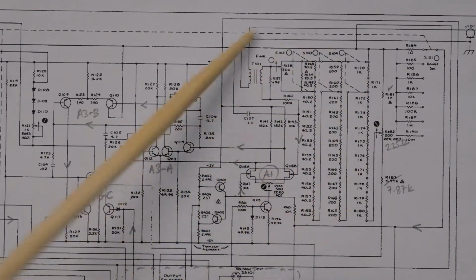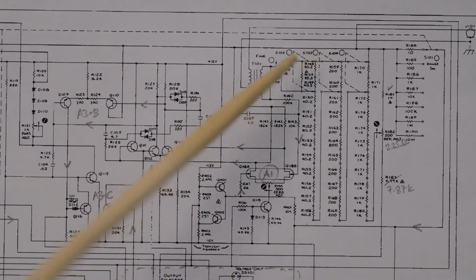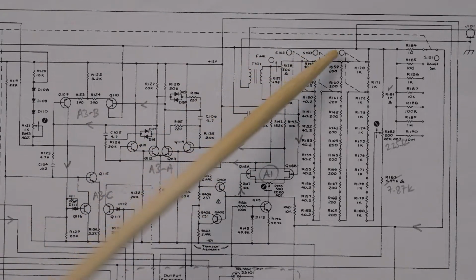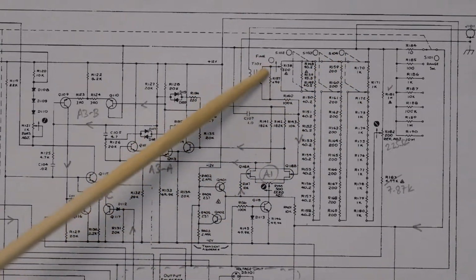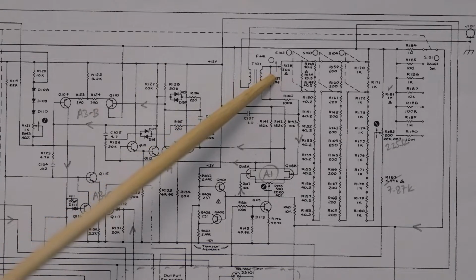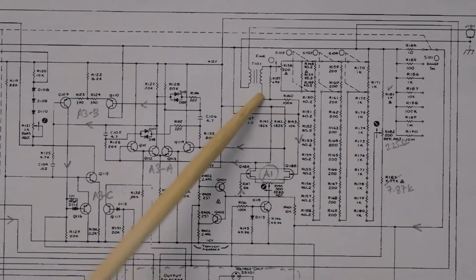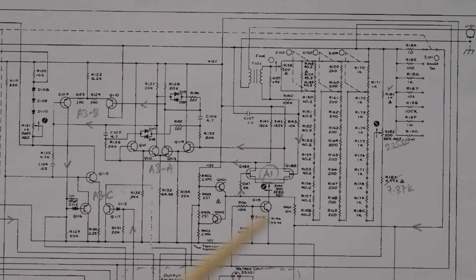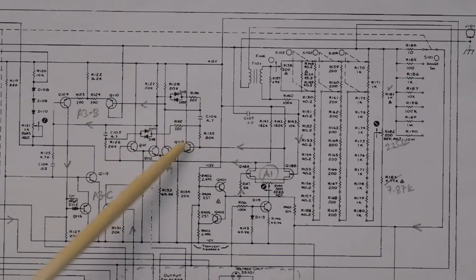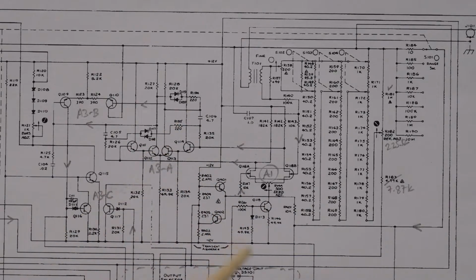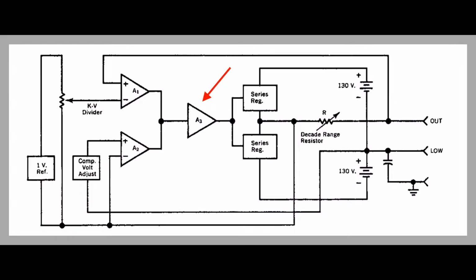So the Kelvin Varley divider is this big resistor network. It's controlled by the 3 switches, which can select different digits from the MSB down to the LSB, plus a fine tune, which is the final potentiometer, which is a variable one, which gives you the 0.02% full scale adjustment. So the output of this Kelvin Varley divider goes into this A1 amplifier, which is really this main amplifier here, whose second input is basically the feedback of the output that is coming from the current source load. So it compares those two, and then that is amplified by this matched FET pair, goes into the second stage, A3A. Sorry, not the second stage, it's basically the A3 amplifier, which is over here, which is also taking the input from the compliance side, but we'll get to that later.